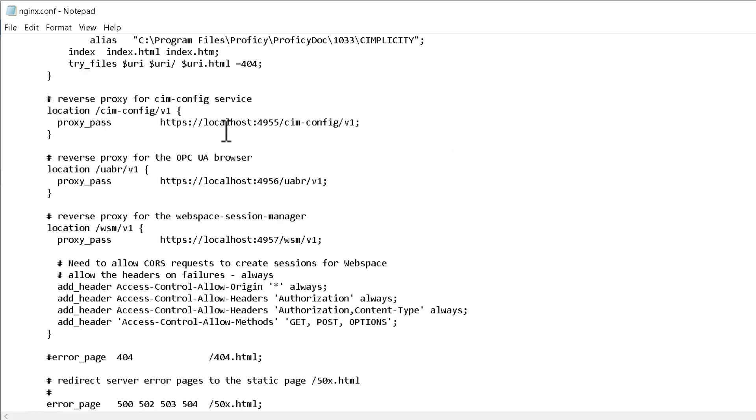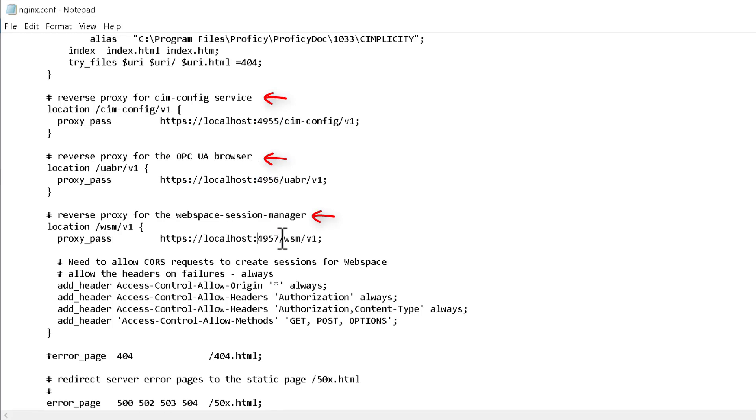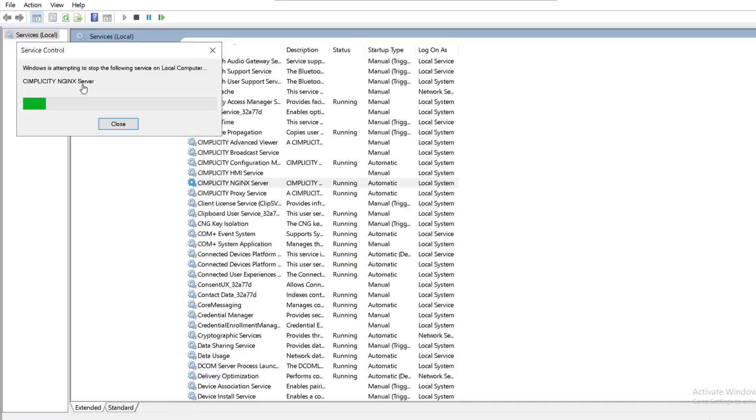Ensure that the port numbers mentioned here for CIMPLICITY Configuration Service, OPC UA Browser, and Webspace Session Manager match with the port numbers entered while processing the certificate. Update the values if required and restart the nginx service to apply your changes.